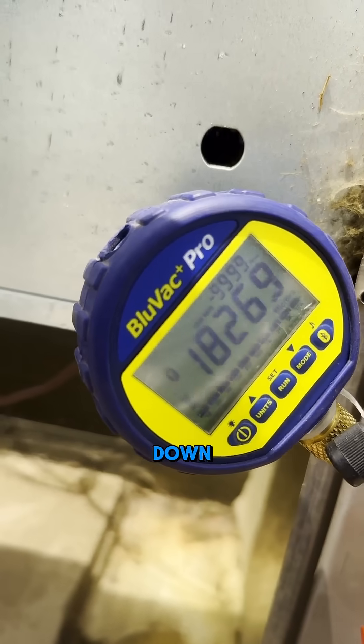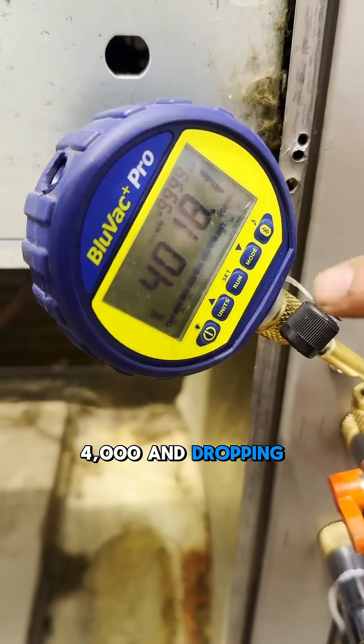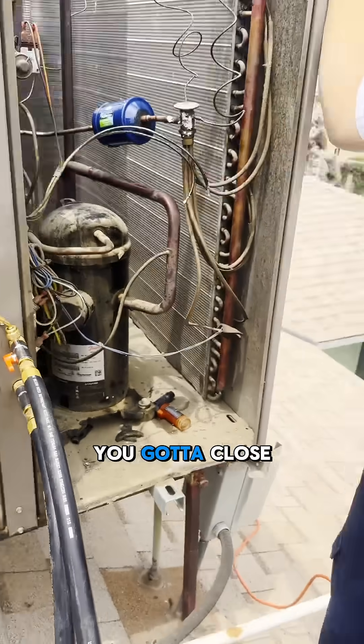You'll see this thing starts dropping down. Like we were just at 20,000 microns, now we're at 4,000 and dropping. And then once you get to three hundred, you got to close the valve here.